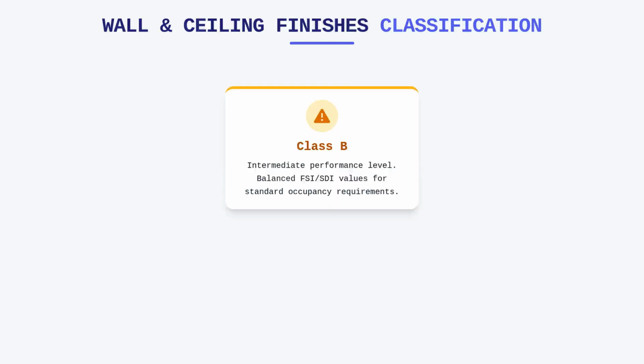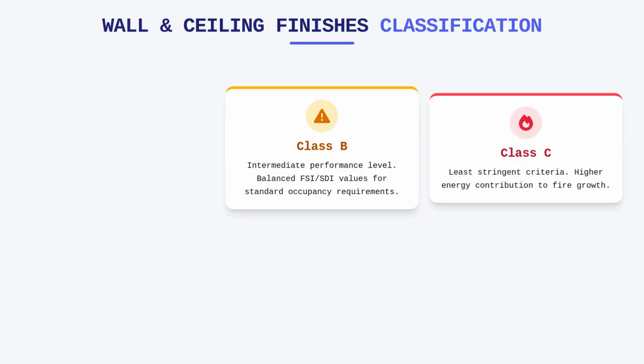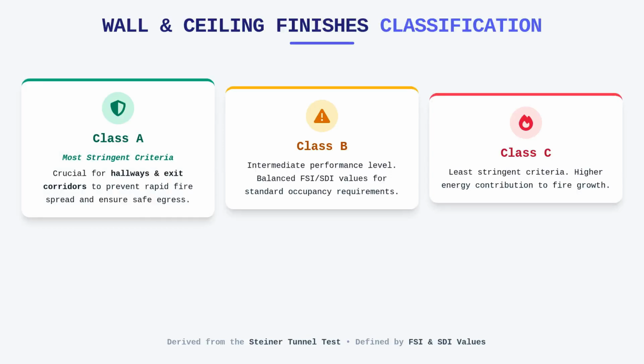The classification system for wall and ceiling finishes is the primary tool that codes use to regulate these materials. Class A, Class B, and Class C classifications are derived directly from the results of the Steiner tunnel test, with Class A representing the most stringent criteria. For instance, in many occupancy types, hallways and exit access corridors must feature Class A materials to prevent rapid fire spread that could cut off an egress route.